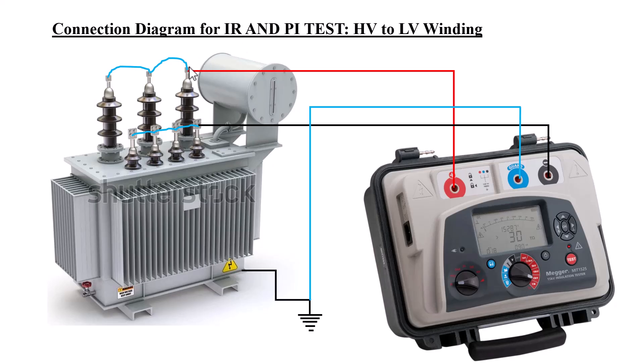For the HV to LV configuration, the positive red lead is connected to the high voltage winding with all three phases shorted together. The negative black lead is connected to the low voltage winding, also with all three phases shorted. The guard (blue wire) is connected to ground, so that the ground effect does not disturb the HV to LV test results. That is the purpose of the guard.